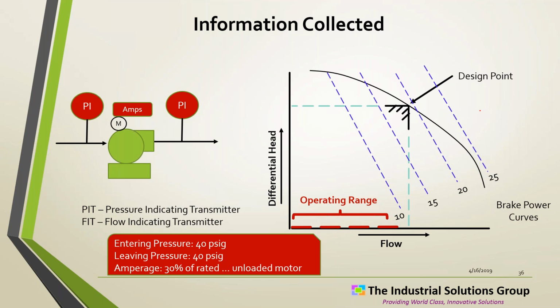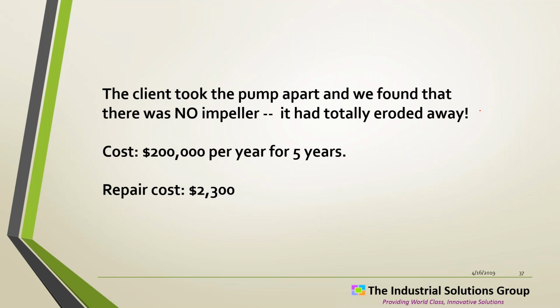We found the entering pressure was 40 pounds, leaving pressure was 40 pounds. And so we had no differential pressure. We were at 0. And the amperage was only 30% of the rating. So we were operating way down in this low flow range. Then we had them pull the pump apart, and absolutely no impeller. This pump had been working for 5 years every day. It was a real soldier, spinning, and all we had was the shaft of the pump left.